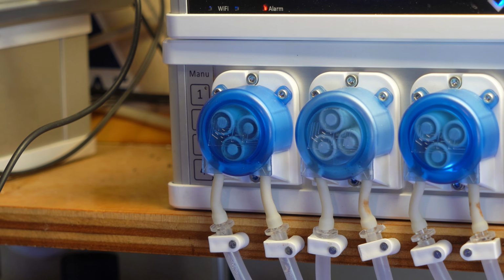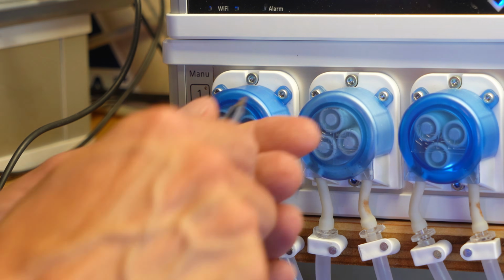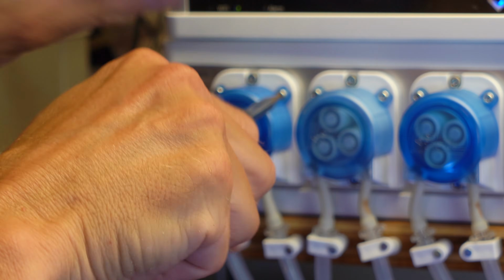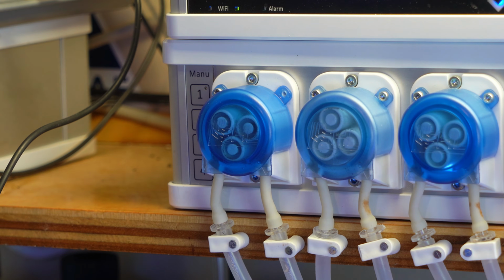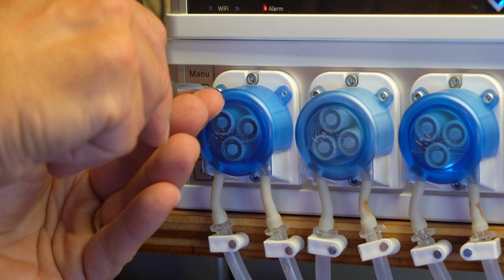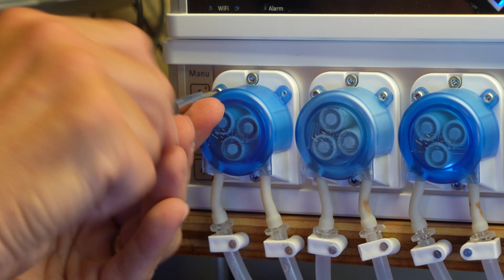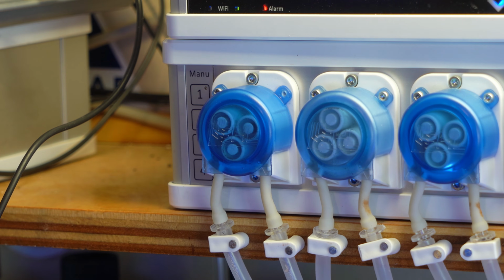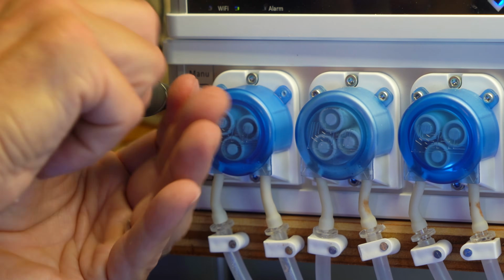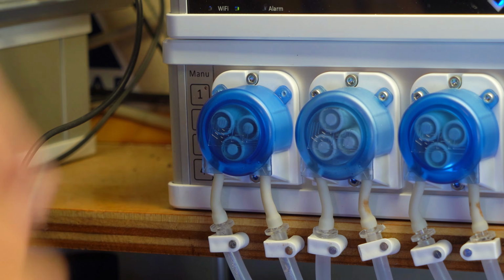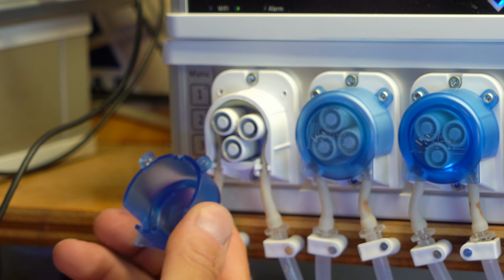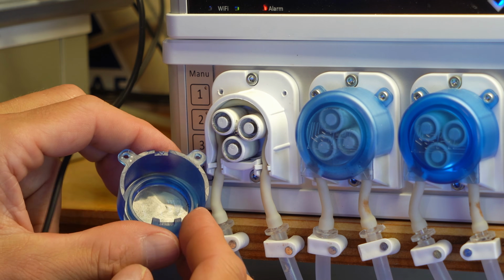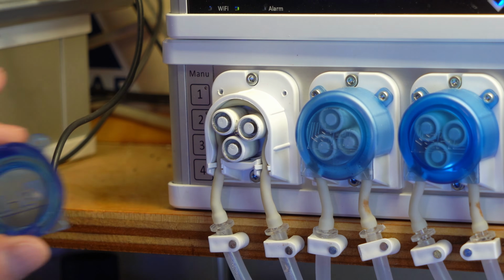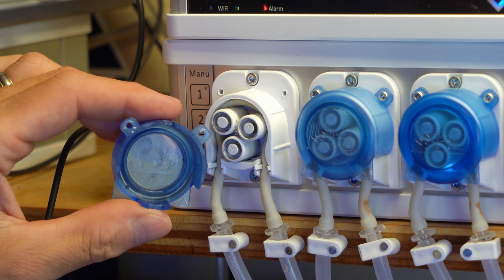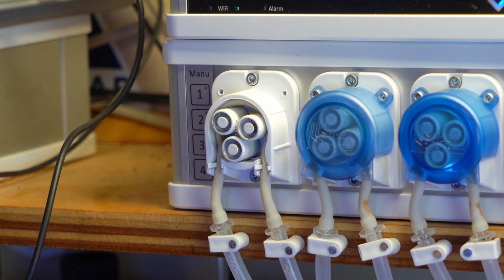Really, the first step in terms of maintenance is taking the covers off. Use this screwdriver right here, and you got to be careful about these screws—they have a tendency to fall off and end up somewhere tough to find, so be careful removing them. Take the screws off, cover comes off. Again, inspect the cover to make sure there's no cracks or damage, and even take a little cloth and clean out any dust and debris inside there.